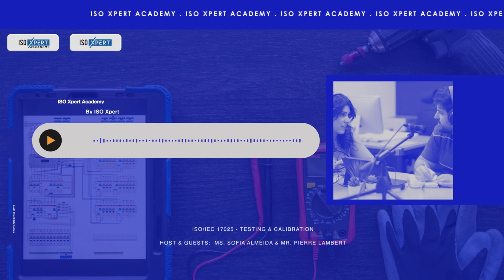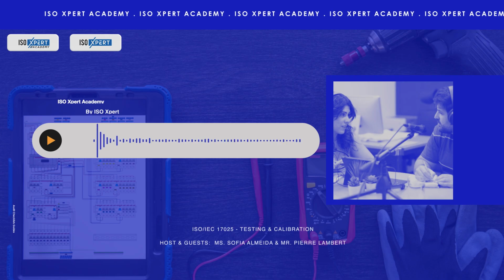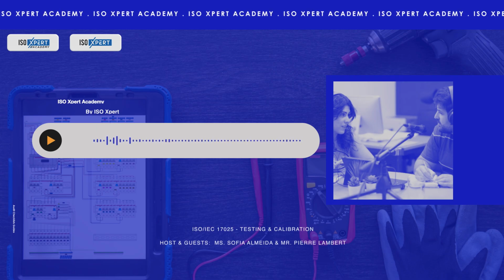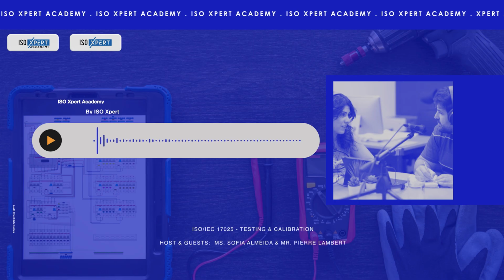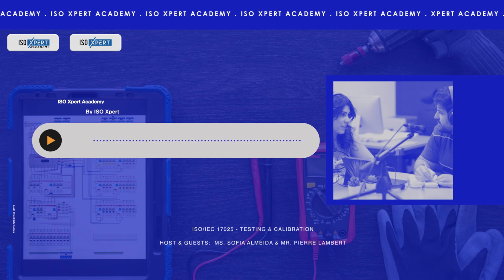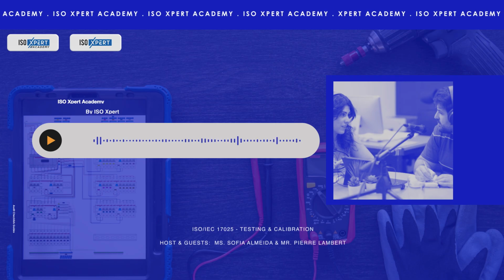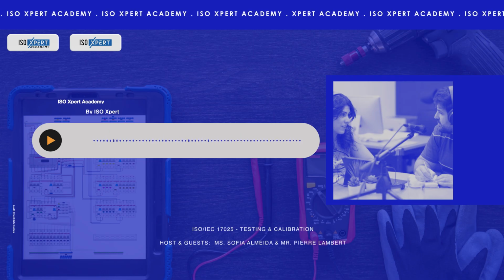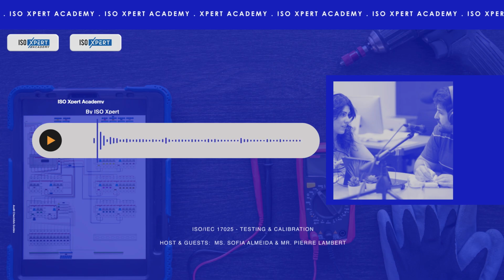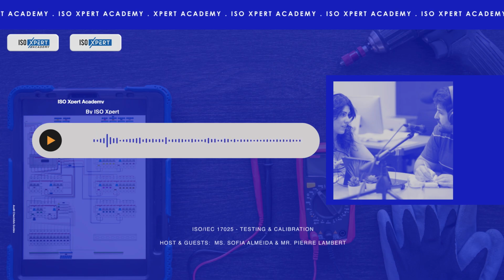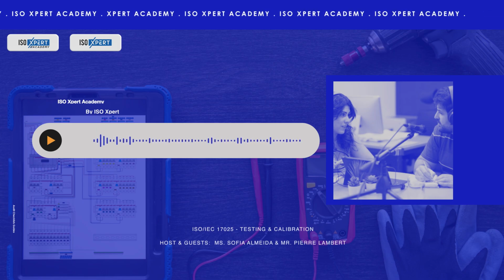Okay, finally, for the management system, how does a lab check itself? Make sure all these systems are actually working as intended. That sounds like internal audits, 8.8, and management review, 8.9. These are absolutely vital self-assessment processes. Regular internal audits, covered in 8.8, are conducted by the lab itself. Auditing themselves. Yes, trained internal auditors check compliance with the standard and, importantly, with the lab's own procedures. It's like putting themselves through a mini audit before the external auditors arrive.